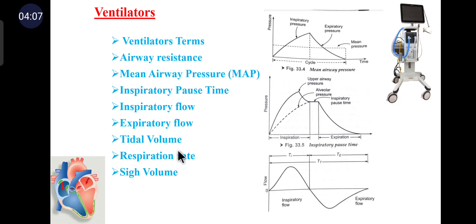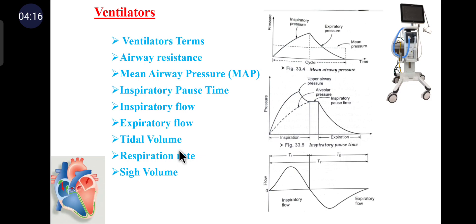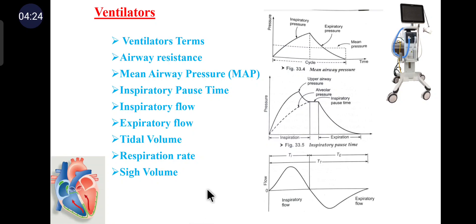Tidal volume is the depth of breathing, or the volume of gas inspired or expired during each respiratory cycle. It can be calculated by multiplying the flow rate by the set inspiratory time in seconds. Respiration rate is the number of breaths per minute and represents the total respiratory rate of the patient.